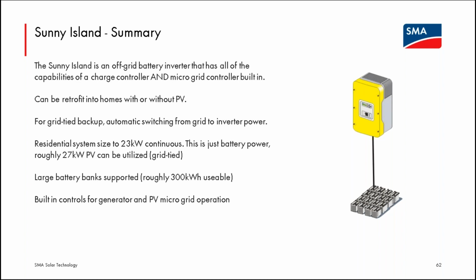If somebody has a firmware for the Sunny Island where they've seen that go away, that would be great. And there is a multifunction relay in the Sunny Boys. There are some settings for that. So I'd love to confirm that someone is talking about the Sunny Island and the 2 programmable relays and having that bat fan setting, or is it one of the default settings removed? And then if so, if there's a firmware version that they've seen it in, I can investigate.